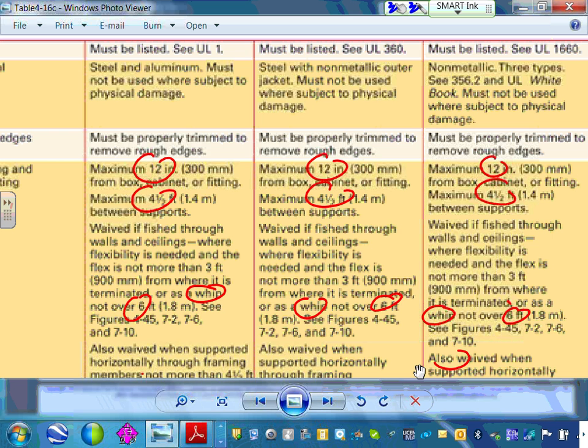Then from this fixture to this fixture, if it's more than 6 feet, they just support it in the ceiling. From this fixture to this fixture, to the third, to the fourth, to the fifth. And by doing it this way, they can only have one box. You don't have to have multiple boxes. Very cheap, easy. The contractors love that way. Easy installation. Fixture to fixture. Any comments, any questions, guys, about the support? So 6 foot fixture whip, no support, otherwise 4.5.